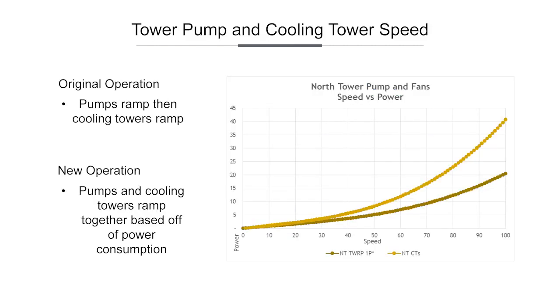Tower and the tower pump. So Kallie mentioned that these SWUD units are a little interesting in that you're actually moving condenser water into the building to get to the SWUD unit, which is then going to do the heat exchange to send onto the cooling coils. In the as-is condition, the pumps would ramp to maximum, and then the cooling tower would start to bring its fan up.